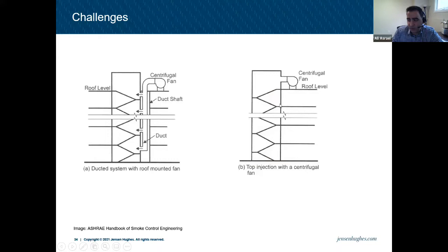If you get to a certain height, more than 20, 25, 30, typically when you go over 20, this fan becomes a massive fan. When you put a massive fan at the top of a stair and inject the air through this shaft, for the first quarter, or the half, or a third of it, mostly the third is pretty fair to say, becomes overpressurized, and it's expected, right? You're putting a massive fan at the top and injecting air all the way down. By the time the air gets to the bottom half, the doors can be opened properly, so the pressure is not that significant. But for the top floors, it's a challenge.